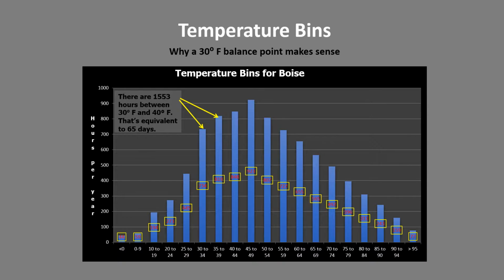So sometimes we hear, hey, how come you make such a big thing about the 30-degree balance point? Does it really make that big a difference? We look at Boise, and Boise is pretty similar to Bend, Oregon, for instance. And what we're looking at here is a bin temperature chart. These are how many hours every year that the temperature is in a certain bin. So between 40 and 44 degrees in Boise, we have 848 hours a year.